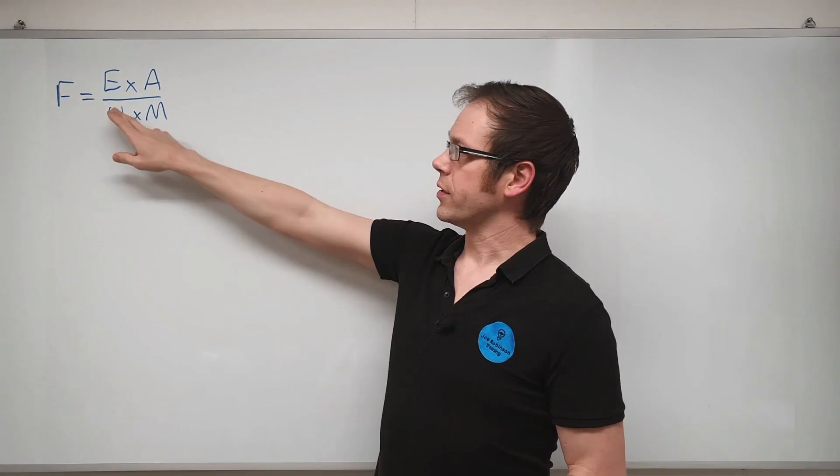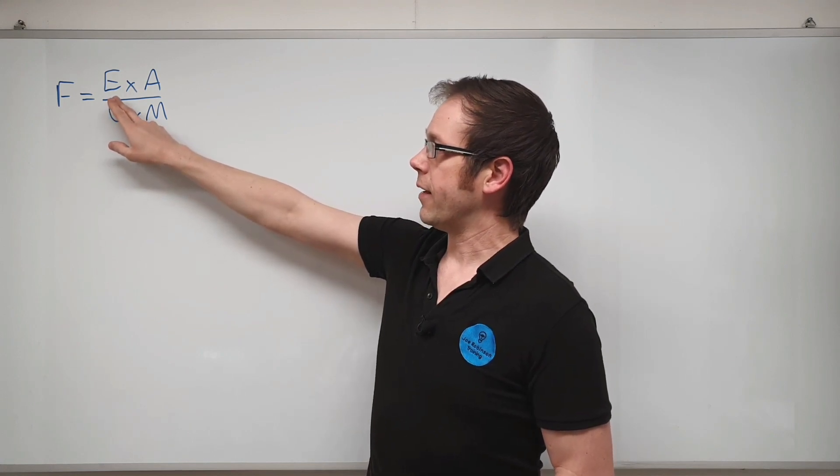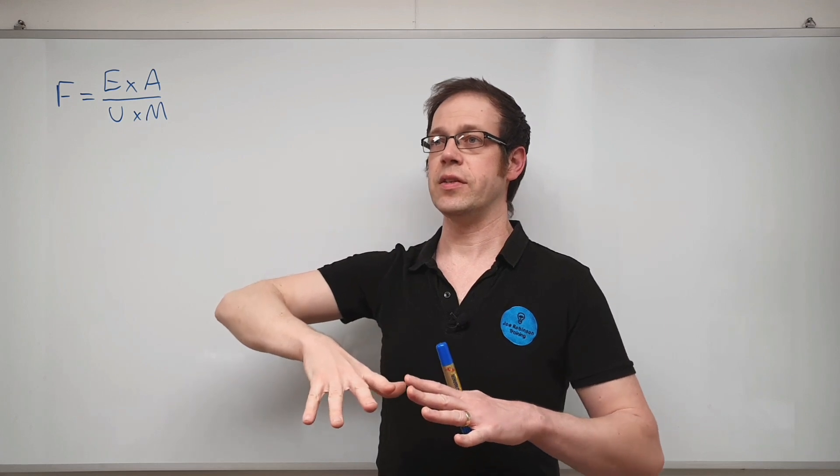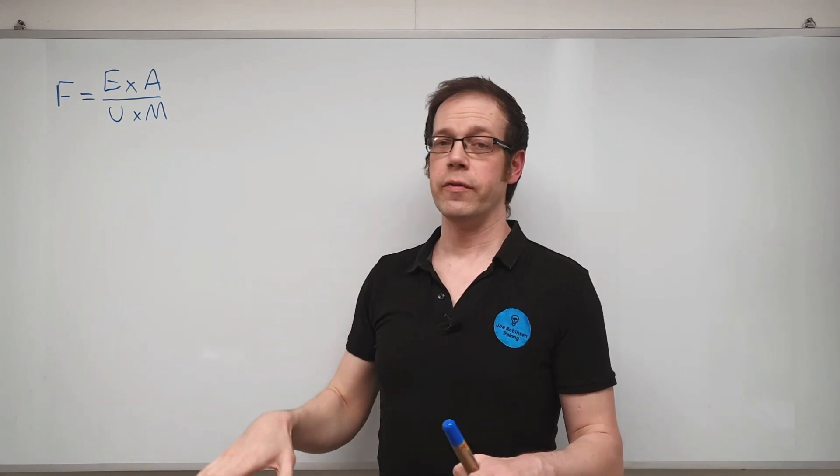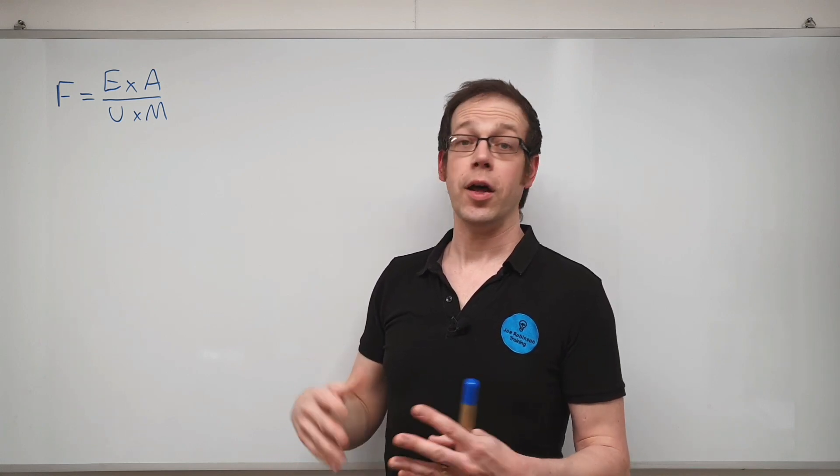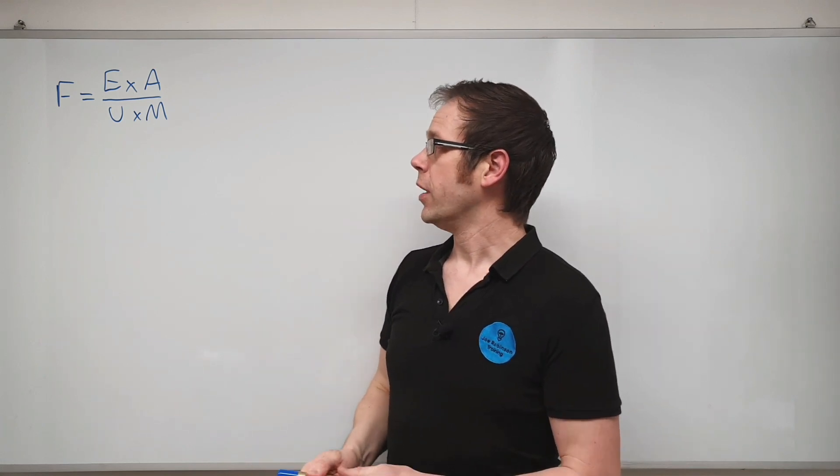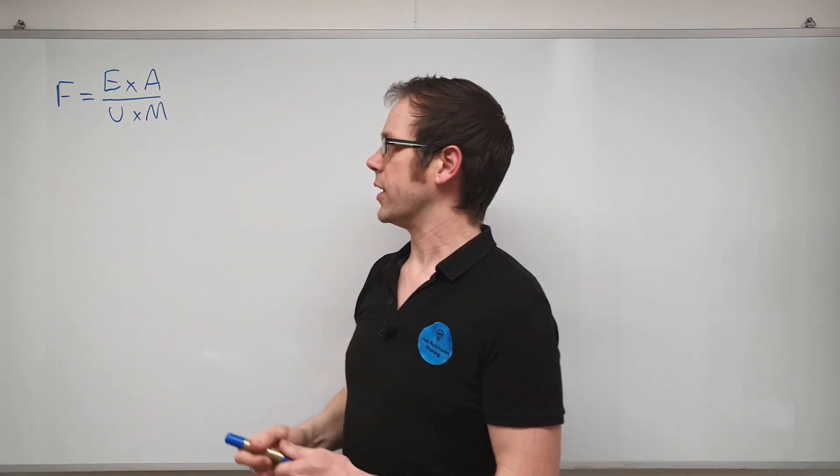Let's say we've got something like a classroom where the surface needs to be illuminated to a level of 300 lux, which is a good value for classrooms that are not being used for night classes. So we would say that we put in 300 there. Let's actually put this into the calculation. We'd say that is equal to 300.